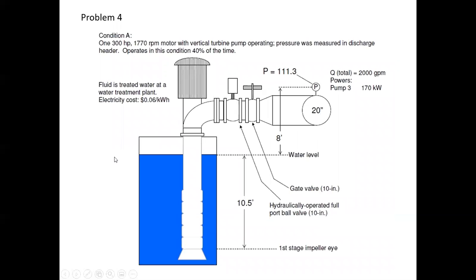Okay, so problem number 4. This is a vertical turbine pump, and so the impeller stages are down here, well below, submerged below the water level in this well. Sometimes these are called wells. So we got 1, 2, 3, 4. It's actually a 5-stage vertical turbine pump. Motor sits up here. It's just on a long shaft. This is the inlet to the pump, and the first stage starts right here.